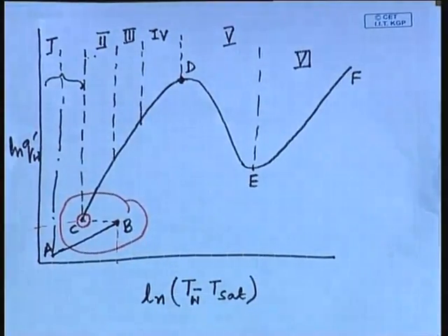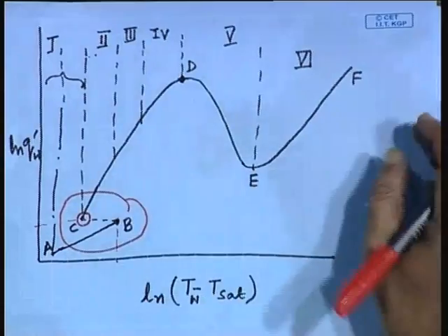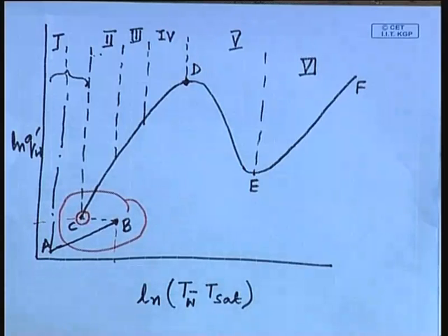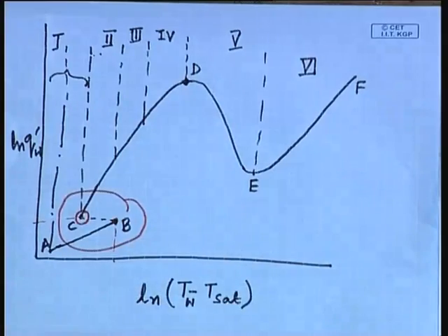Now, different regimes of boiling I have told, and one thing is important here, where we operate. In most of the industrial practices, we operate in the nucleate boiling regime, and in the nucleate boiling regime also we can find there are different sub regimes. First we have the regime of isolated bubbles, then the regimes of slugs and columns, then these slugs and columns merge together and we get a fully developed nucleate boiling kind of a thing.